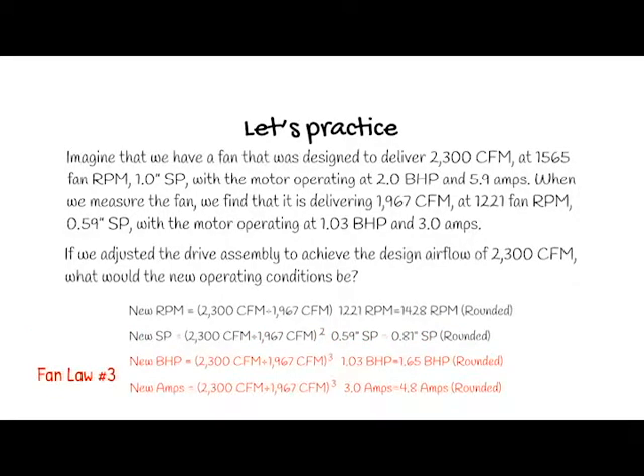Brake horsepower and amps utilizes fan law 3. We use 2,300 divided by 1,967, cubed. We multiply that by the brake horsepower of 1.03, which gives us 1.65, or by the amps of 3.0, which gives us a new amp draw of 4.8.